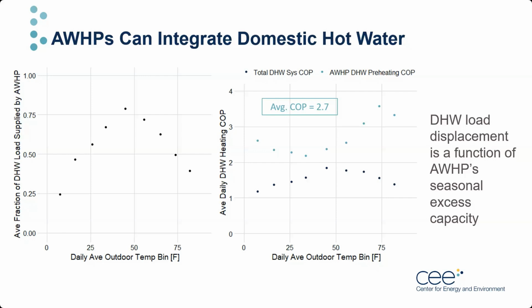The average daily DHW preheating cycle COP measured was 2.7, although higher COPs were measured in warm weather above 70 Fahrenheit, as you can see in the chart on the right. The left chart shows the fraction of domestic hot water heating provided by the air-to-water heat pump. Because of the unusually large domestic hot water load at this site, we can say that the average residential customer might expect an air-to-water heat pump sized for space heating to be able to supply up to 100% of the whole domestic hot water load. That is for daily temperatures ranging from approximately 20 to 80 Fahrenheit. Beyond these temperatures, an auxiliary domestic hot water heater likely still remains necessary.